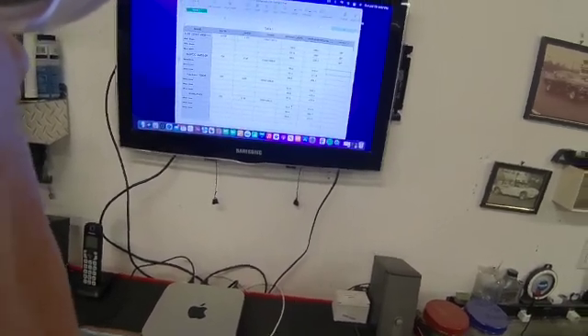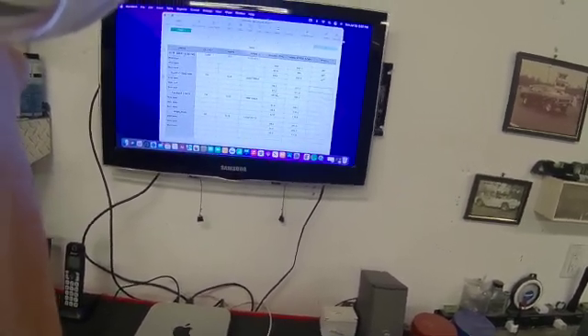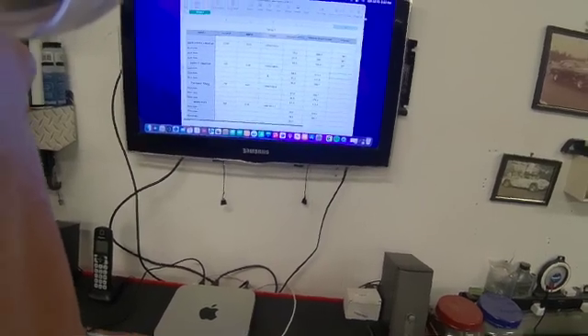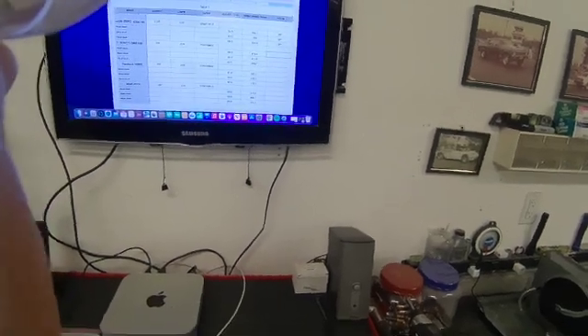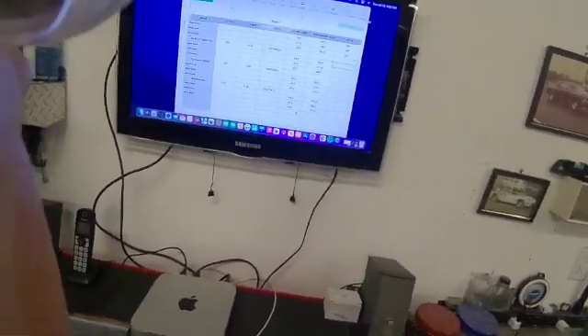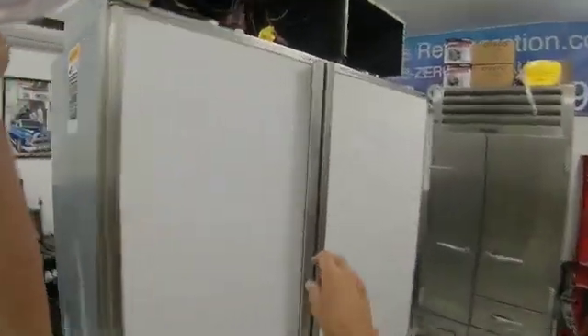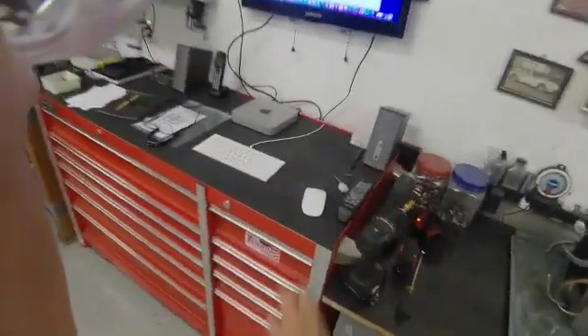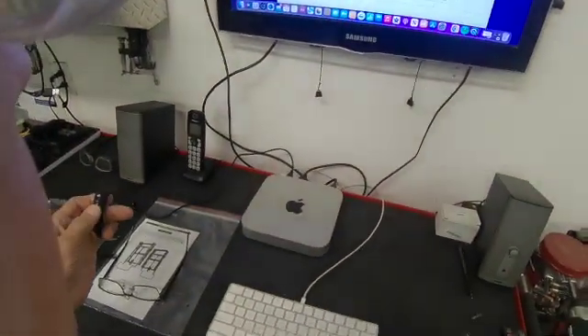So you could see that as far as sound level is concerned, and that's what's really important when you're using the Packard and the Supco motors. You see what the factory is, 59.5 with the black blade and with that speed motor. So there's your difference. The Packard and the Supco motor are much stronger motors. They turn faster, so they're going to make more noise, and they're going to pull in more air. So those are the stats. Take a picture of it. Keep it on your phone if you ever want to refer to it. There are some other motors that we use out there. For instance, I have a 632 here in the shop, it's got a Fasco motor on it, and I have a 611 here that has a GE motor. I'm sorry, that's the factory motor. So that's where we're at. I think I covered all of it. If you have any questions, feel free to contact me. Have a good day.